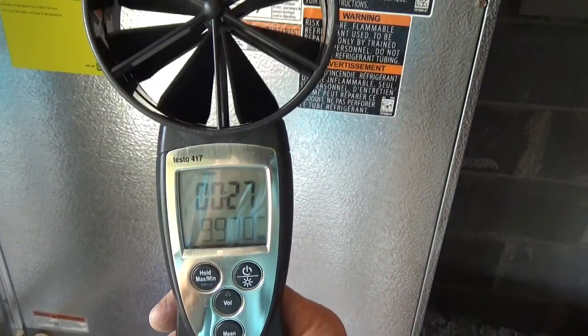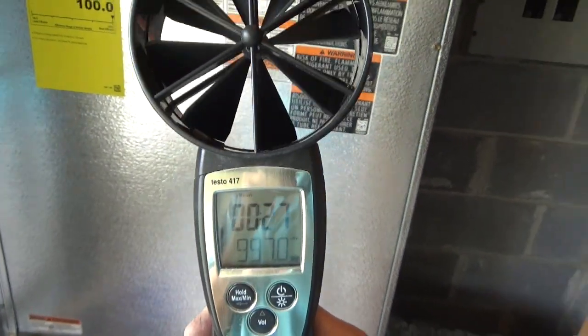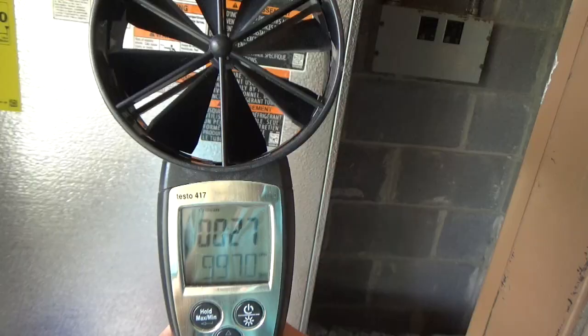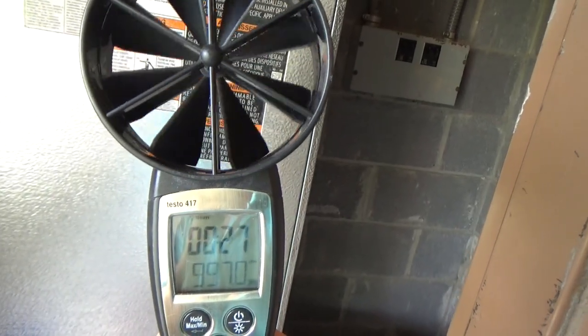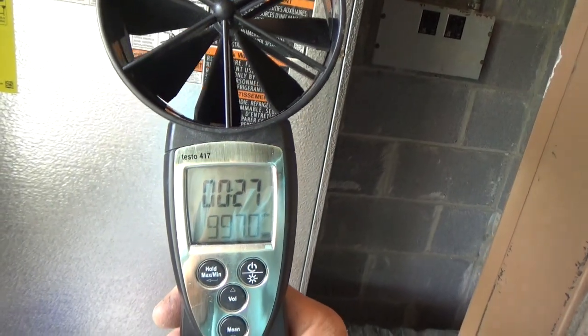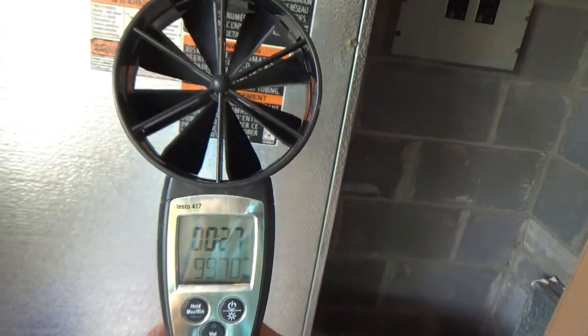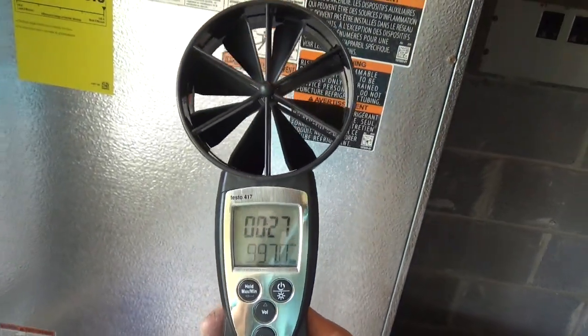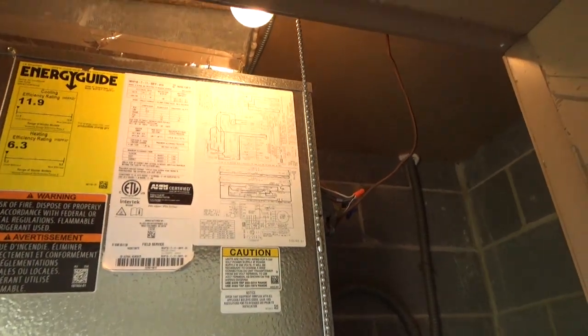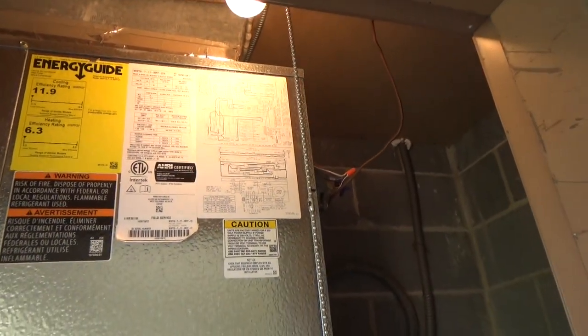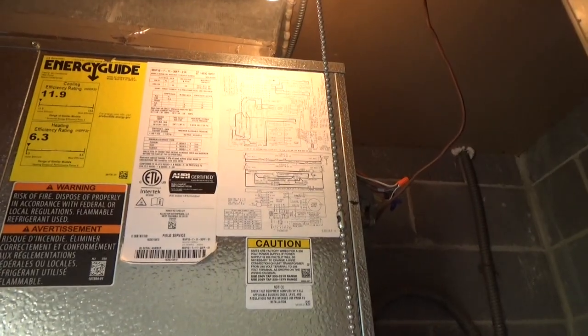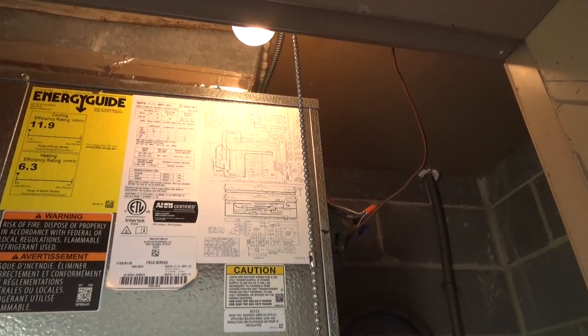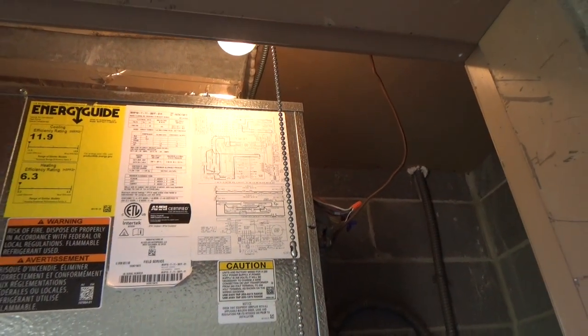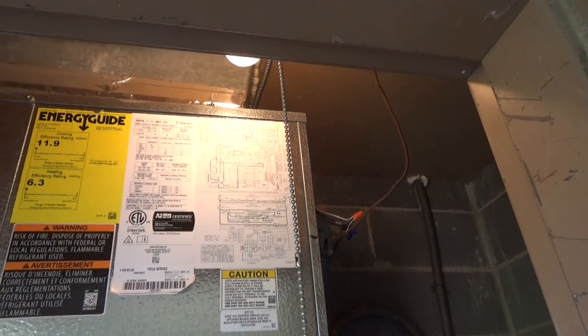So I had to run the black wire. And for the auxiliary heat, I'm gonna run the second to the highest, which is the 960. It's a little bit lower on the airflow, but auxiliary heat's not gonna run very often, and the weather will be cooler anyway, which means the pressures will be lower when it runs the auxiliary heat, and that'll be fine. And actually a little bit lower is probably going to make the air a little warmer anyway.